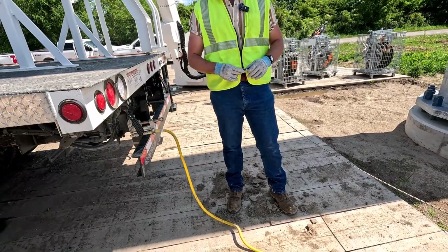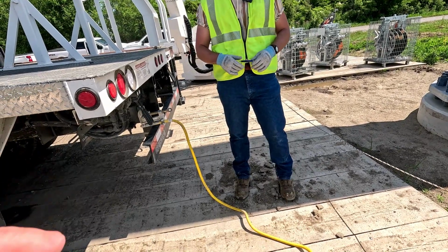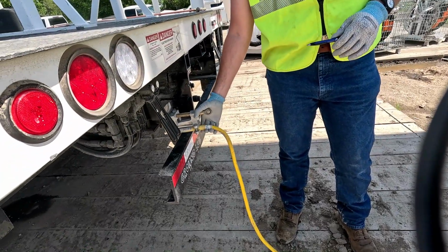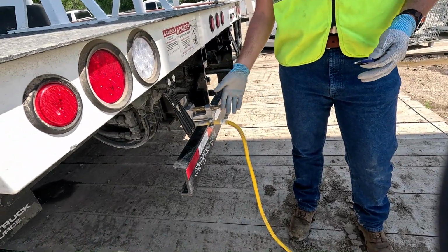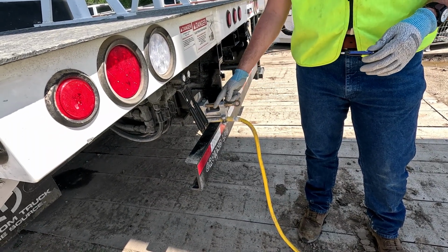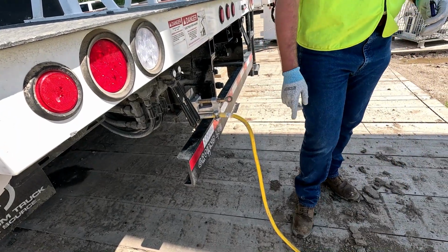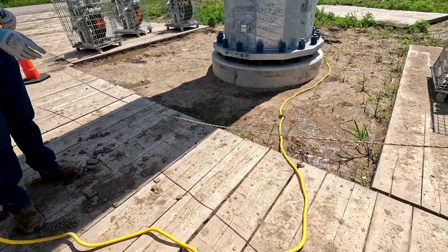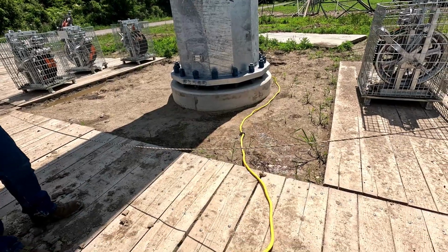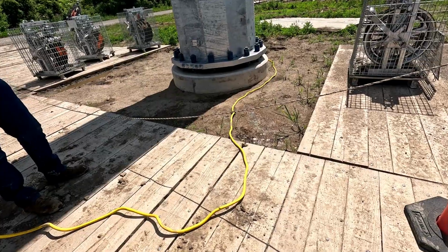So what are some of the key points you look at when you're doing an audit or inspection to ensure the crews are safe? What do you look at on this ground? So one thing that I look at is making sure that these are on tight. They don't have to be super tight, but just tight enough that they won't fall off. A loose ground is a faulty ground, right? Another thing that we look at is inspection dates and also making sure that the wire is not coiled up to create induced voltage. Oh, that's right. So if it's coiled up, it can multiply the voltage and cause a problem.